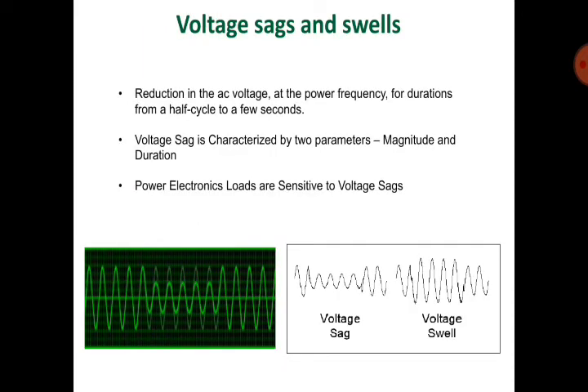Voltage sags and swells: a reduction in the AC voltage at power frequency for durations from half a cycle to a few seconds is considered a voltage sag. Voltage sag is characterized by two parameters: magnitude and duration. In the waveform, the amplitude in a certain portion is lower than the normal value — that portion is a voltage sag. A voltage swell is where the amplitude of the voltage increases for some cycles.